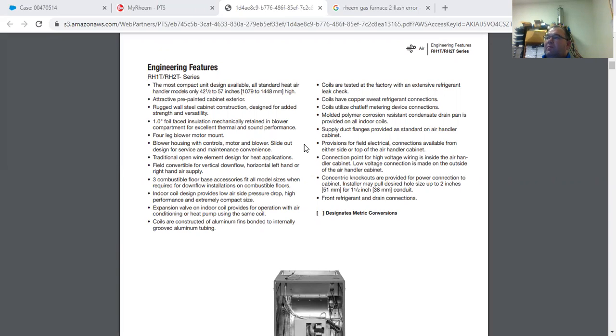You do have a 4-leg blower mount, which is important. Gives you a more rigid and stable mounting for your blower. Blower housing with controls, motor, and blower. Good feature. It's a slide-out design for easy service and maintenance. It does utilize the traditional open element design for heat pack applications. It is field convertible for vertical downflow, horizontal left, and horizontal right. So it's pretty versatile. It will come out of the box in an upflow position.